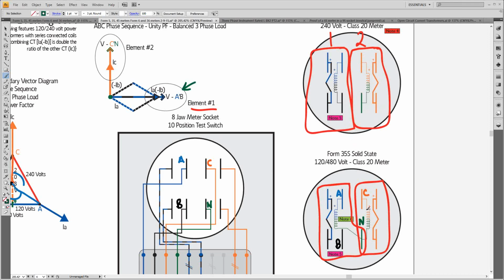And so what happened is we had some of these meters come out when we first started buying these ABB meters. They were marked as a 5S. They were wired just like this. And the meter manufacturer, we started installing them. Wally, I think, was involved with that part of it. As the process started to come about, there was an identification that that 5S meter wired that really was a 35S. It wasn't this meter. Because it was an auto-ranging meter, the potential coils had to have a common tie for them. So it really was a 35S.